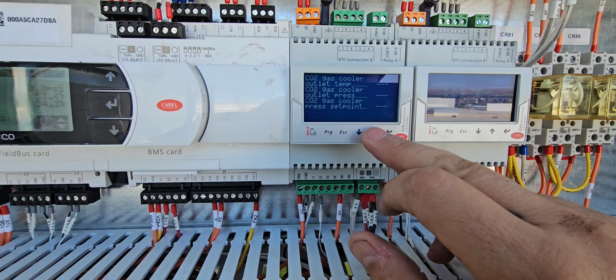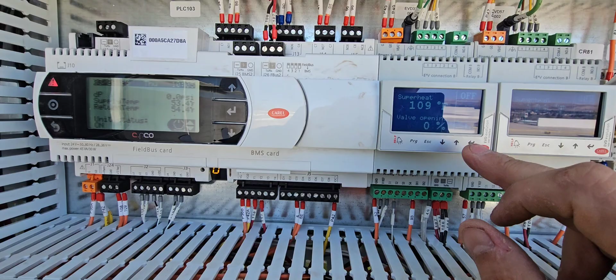But this basically just tells you everything in regards to the valve, and it actually controls the valve. So it gets signal basically from the controller to the valve driver. The valve driver drives the valve open or closed for what superheat you want to maintain, and the way that you kind of check that is in this controller.